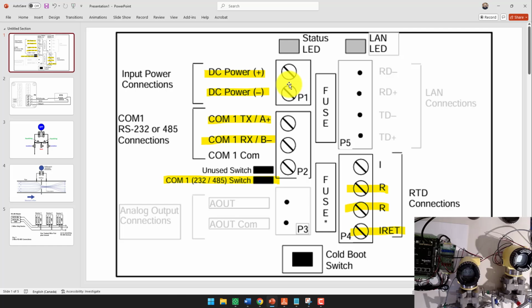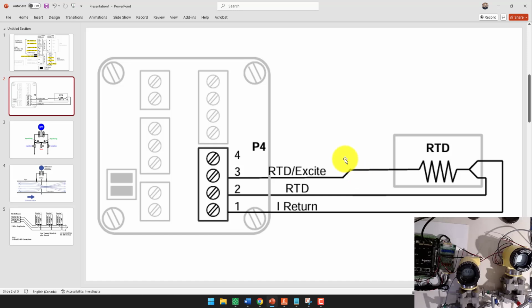We connected this 4102 in the same way, so you have power to power up the device. You have your 485 network, which you have your positive negative that we just went over. Make sure you have the switch selected. I had this selected to 232. Took me a couple minutes to figure out why it wasn't working, so I switched it to 485. And then we have the RTD connected just like we did in the previous 4102. You have your white wire here, which goes to one side of the RTD, and then your two red wires that come back from the other side of the RTD.